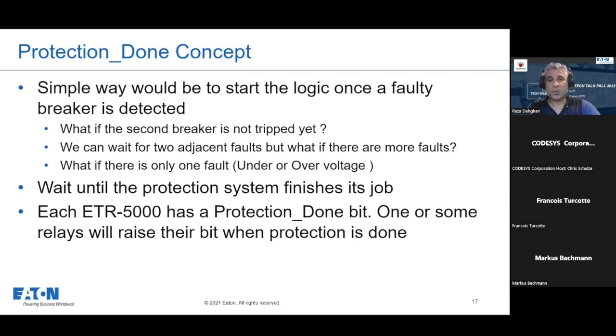One solution would be to wait for 2 adjacent faults. But what if there are more faults? How do we know if there were 3 trips, 4 trips, or 2 faults at the same time on the system? What if there's only 1 fault? This can happen when there are under or over voltage faults on the first and the last breaker. So the idea of the protection done concept is to wait until the protection system finishes its job.